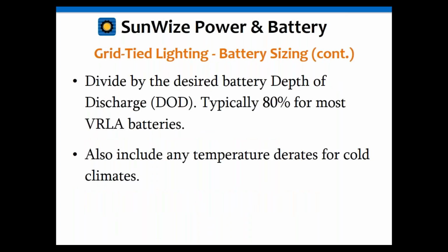Okay, and then you're going to want to divide that by the depth of discharge. As you mentioned, there's usually a low voltage disconnect in these. You want to protect the batteries from being over discharged. For most batteries, that's going to be at the 80% point, so you're only going to use about 80% of the batteries. You're going to take the amp hours that you just calculated. So again, that's the load times the number of hours of backup time you want. You can divide that by 80%. That's going to give you your desired battery capacity that's required.